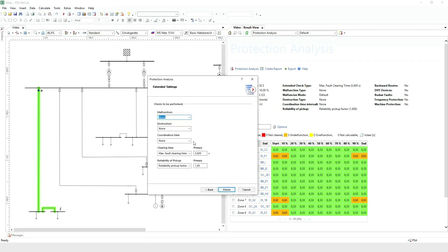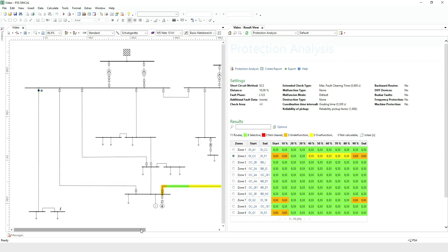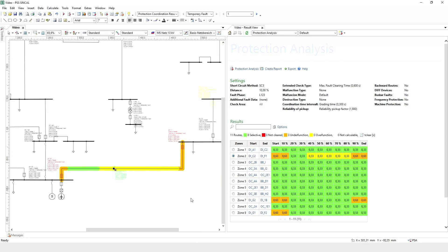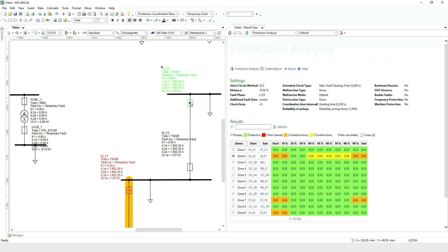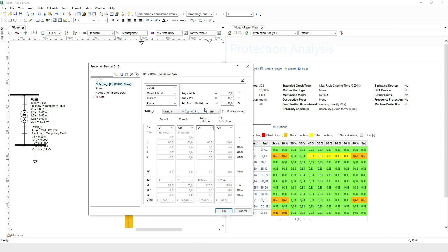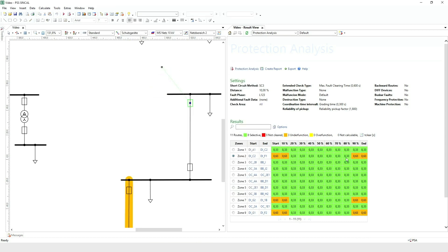The third important check is the check of the coordination time, which looks at time selectivity between devices. There are different modes for this; in this example we'll use the grading time mode. The time distance between two devices should be at least 0.3 seconds. In the results, we see a violation of the selectivity. Performing the protection simulation, the yellow protection device tells us there's a violation of the time selectivity. In the network graphic, we can see the time distance between device DIG1, with a tripping time of 0.5 seconds, and device DIF1, with a tripping time of 0.3 seconds, is 0.2 seconds — below the set 0.3 seconds. So we change the time setting and perform a protection analysis again. The violation no longer exists.